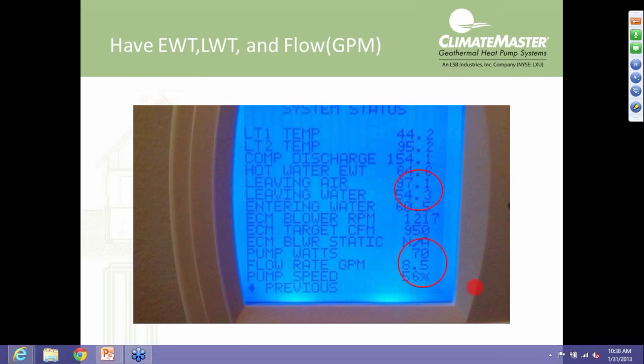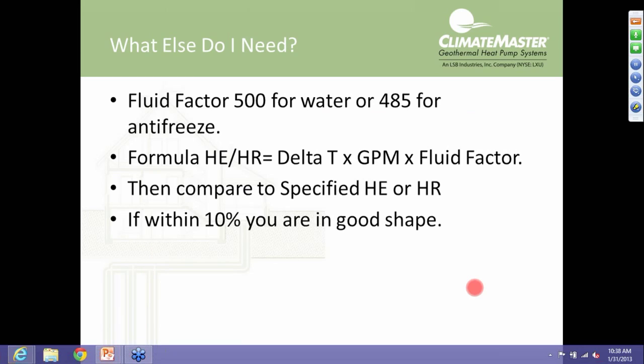Here's that formula I was talking about a moment ago. We've got our fluid factor of either 500 for water, or if we've got an antifreeze solution, we're going to use 485. The formula for either heat of extraction or heat of rejection: heat of extraction is the heating mode, and heat of rejection is the cooling mode. Delta T times gallons per minute times fluid factor gives us how many BTUs we're either extracting or rejecting to the earth loop. We then compare that to the specifications that we just looked at. And again, if we're within 10%, that unit is running just fine. There is no need for putting gauges on or doing further service to the heat pump. The heat pump is doing what it needs to do.